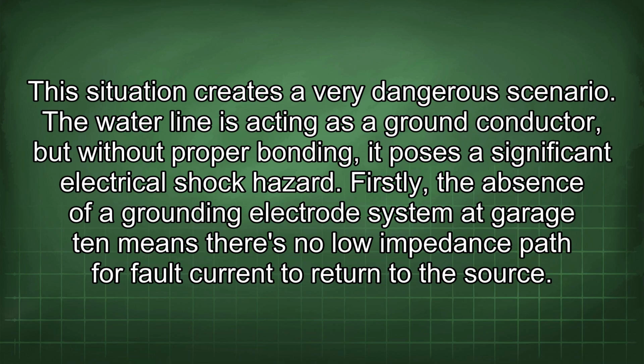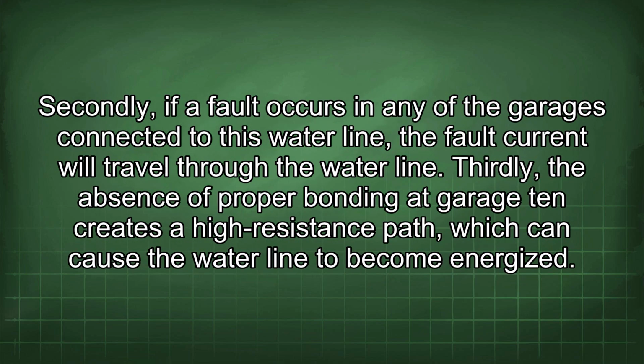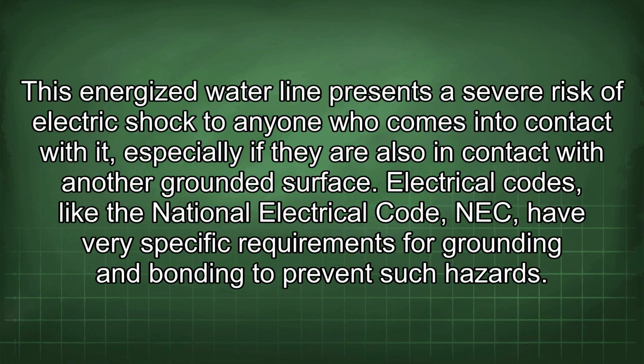Firstly, the absence of a grounding electrode system at garage 10 means there is no low impedance path for fault current to return to the source. Secondly, if a fault occurs in any of the garages connected to this water line, the fault current will travel through the water line. Thirdly, the absence of proper bonding at garage 10 creates a high resistance path, which can cause the water line to become energized. This energized water line presents a severe risk of electric shock to anyone who comes into contact with it, especially if they are also in contact with another grounded surface.